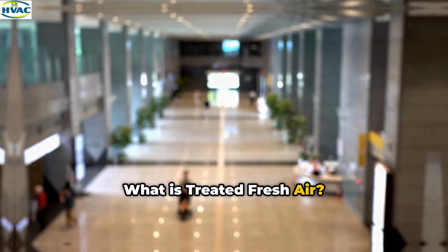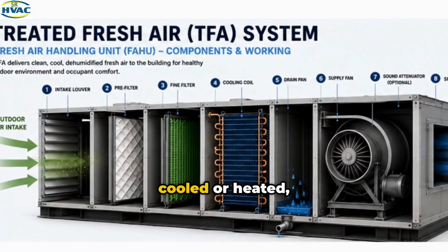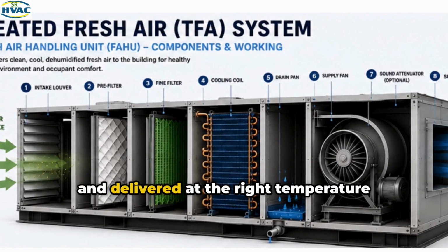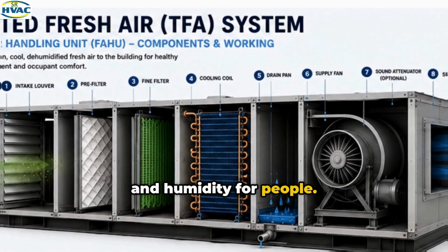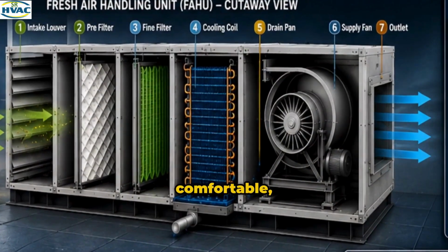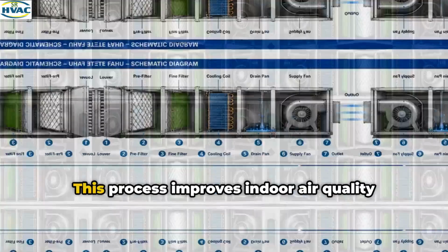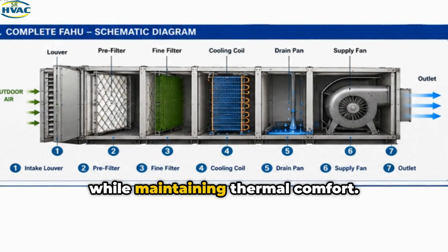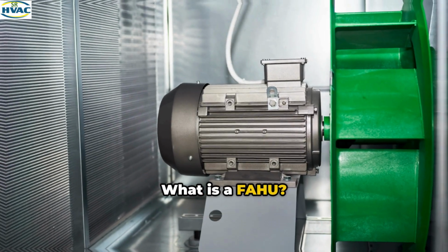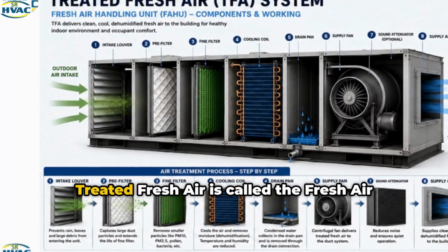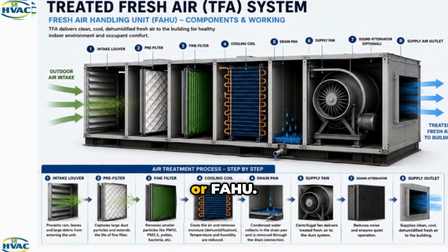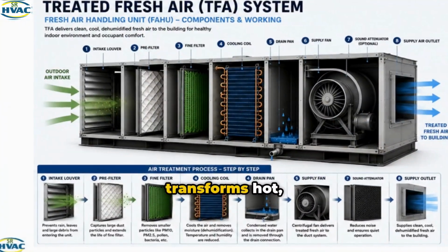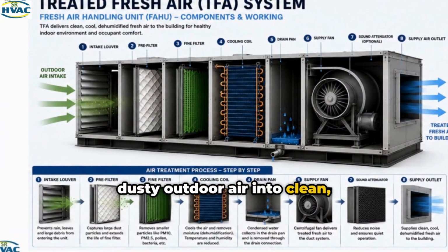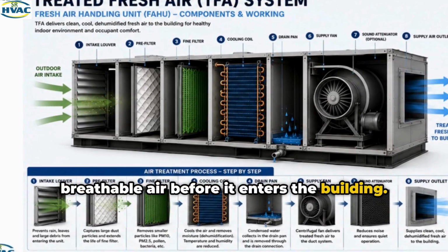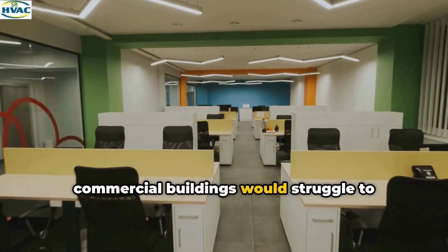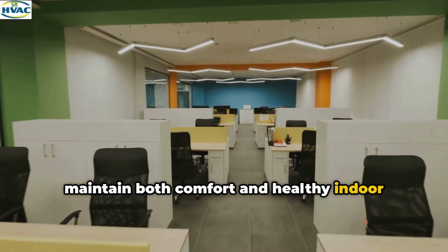What is treated fresh air? Treated fresh air is outdoor air filtered, cooled or heated, dehumidified and delivered at the right temperature and humidity for people. In simple words, it is clean, comfortable, healthy and conditioned outdoor air. This process improves indoor air quality while maintaining thermal comfort. What is a FAHU? The equipment responsible for producing treated fresh air is called the Fresh Air Handling Unit or FAHU. Think of the FAHU as a machine that transforms hot, dusty outdoor air into clean, cool, breathable air before it enters the building. Without a FAHU, commercial buildings would struggle to maintain both comfort and healthy indoor air quality.